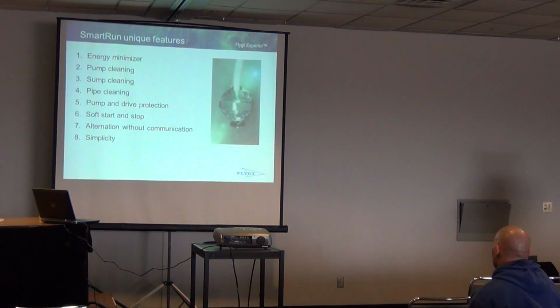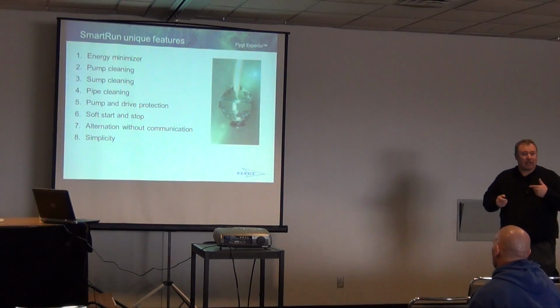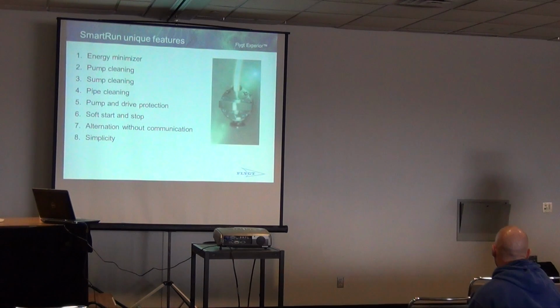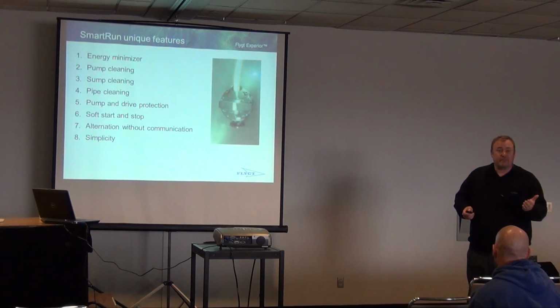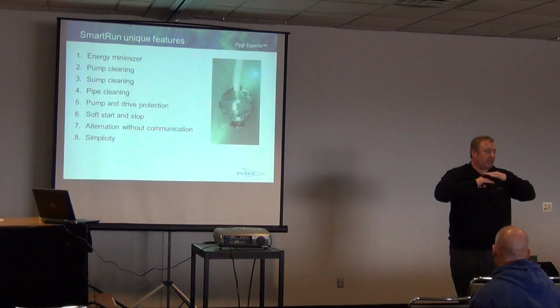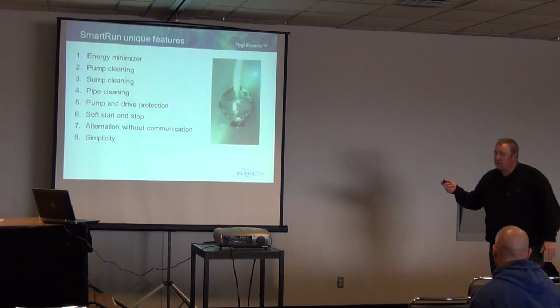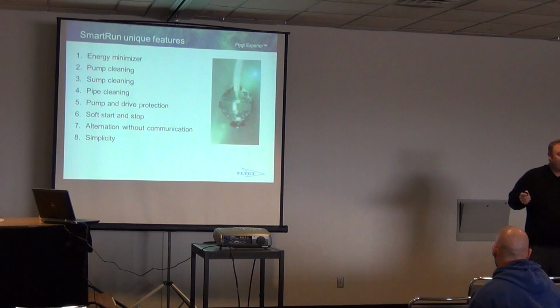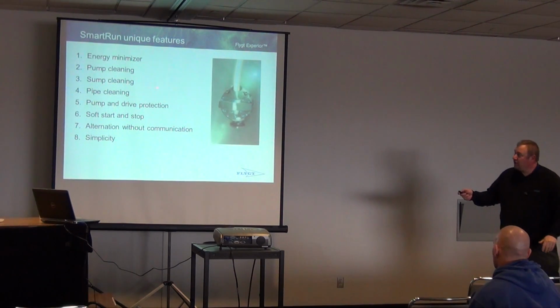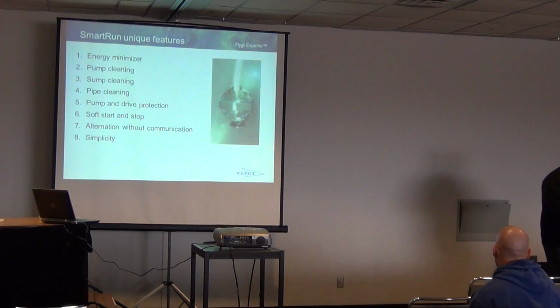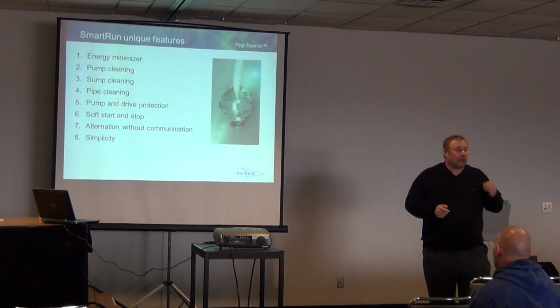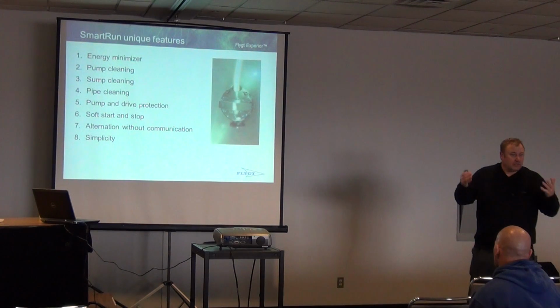It has sump cleaning function. We learned this from our mining experience at Flygt, where we did a lot of sumps and mines, underground mines, is that we needed to get the pumps down to a snore condition once in a while to keep those sumps clean. It's no different in the wastewater stream. It's no different than you going out to your pump station, putting your station in hand, running it down to that snore condition, and what that means is right where that pump breaks suction. What this unit will do is sense an amperage change when it actually hits snore, and before it gets to a point where it can airlock, it will shut it down, but it actually helps keep your sump clean. It'll take it down on however many cycles you want to program. You want it done once a day, you want it done once a week, it's got that sump cleaning functionality in it, helping keep settleable solids, greases, and things like that cleaner in your sump.